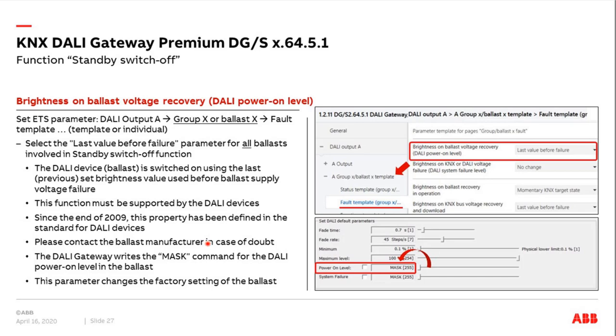When we set the parameter 'last value before failure' in ETS, the DALI gateway writes this information into all the ballasts — the power-on level is set to 'mask'. Using a special tool like the DALI Master Configurator, you can read out all settings of an individual ballast and see the power-on level is set to mask. If the value cannot be changed, you may need to replace the ballast.